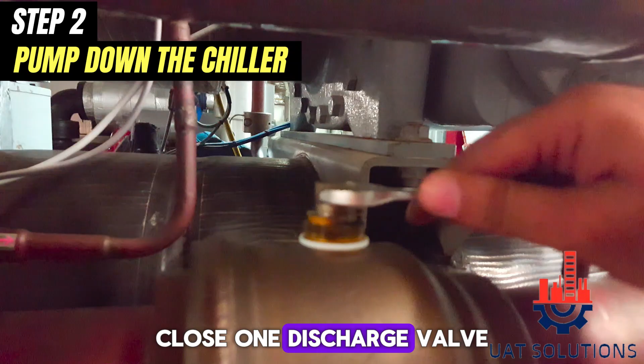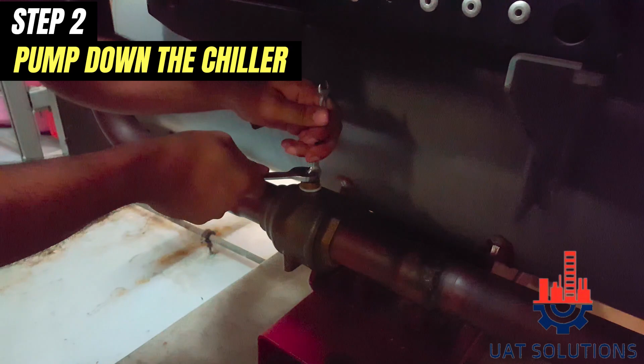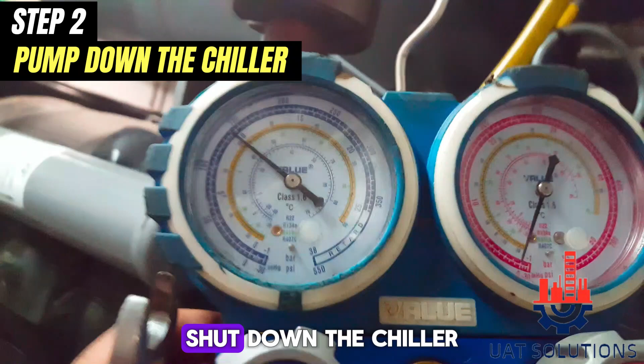Let's start with pumping down the chiller. Close one discharge valve. And close the liquid line valve. Then start the chiller and monitor the gauge. Once the pressure is at 5 psi, shut down the chiller and close the second discharge valve also.